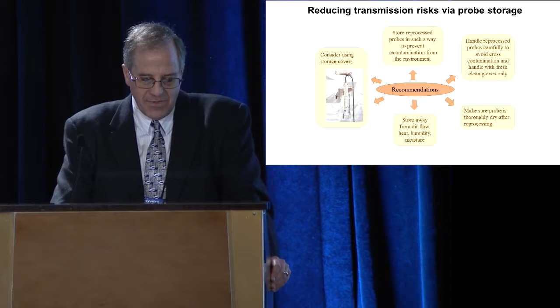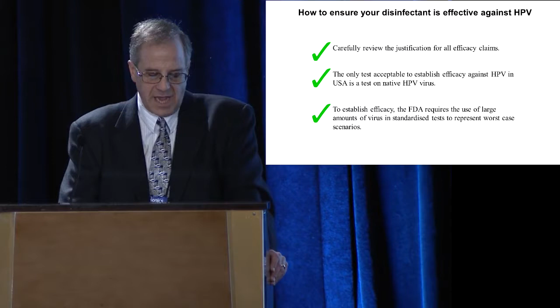Okay, so how to ensure disinfectant is effective against HPV? Carefully review the justification for all efficacy claims. I've walked around when I come to these meetings, APIC, this meeting, and the group in France, I see claims that it kills HPV, and when they've never tested it. In Germany, they will tell you it kills HPV because it kills SV40, a non-human virus. So, you got to really look at these claims. In Canada, they have claims that all these disinfectants work on their disinfectant sheets, but there's no data to back it up. The only test acceptable to establish efficacy against HPV in the US is the test on native HPV virus. There are surrogate recombinant particles out there. We tested those. They are not the same. To establish efficacy, the FDA requires the use of large amounts of virus in standardized tests to represent the worst case scenario.